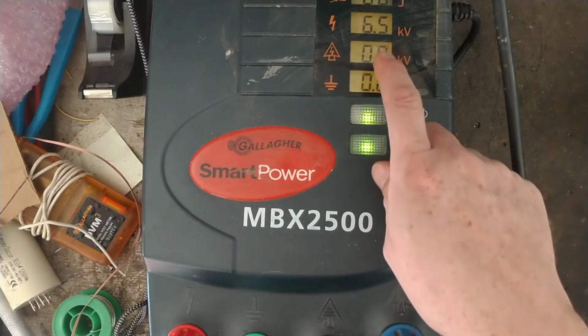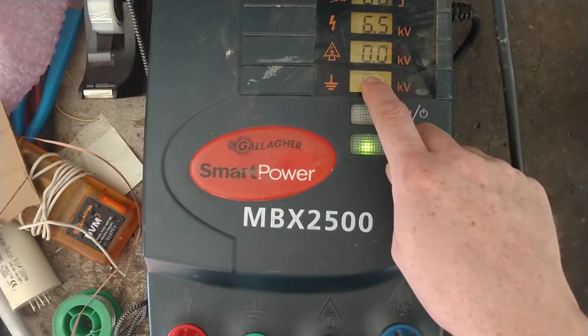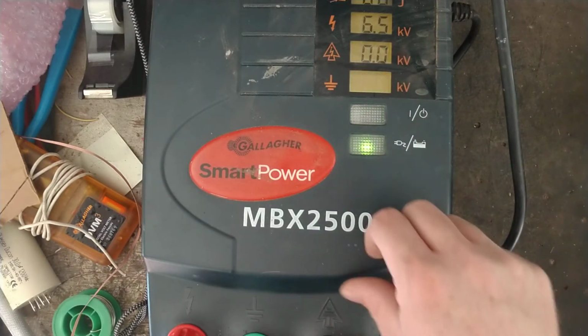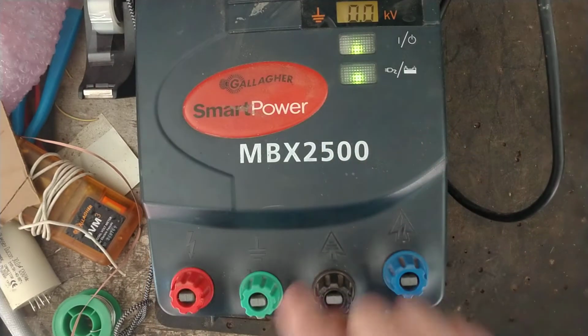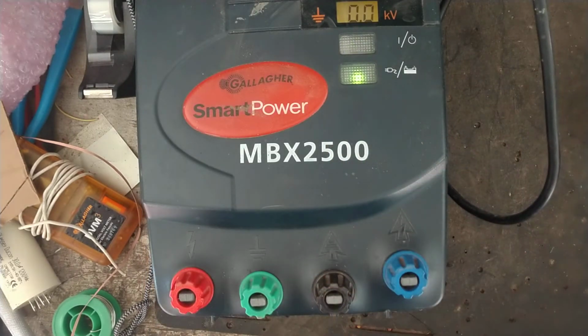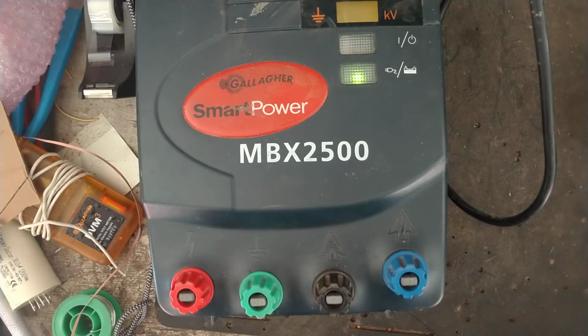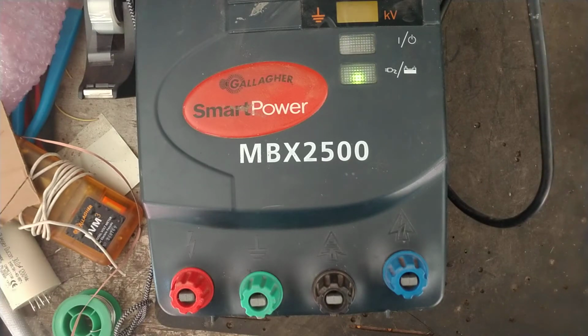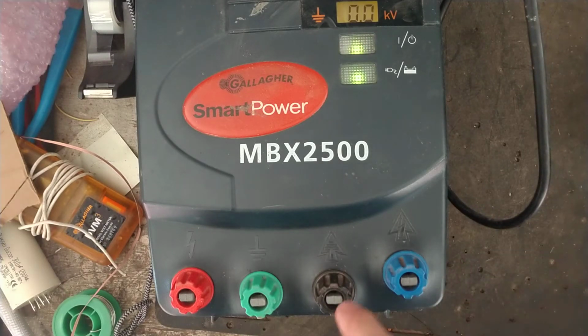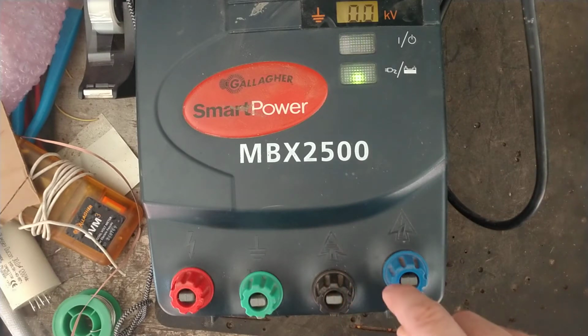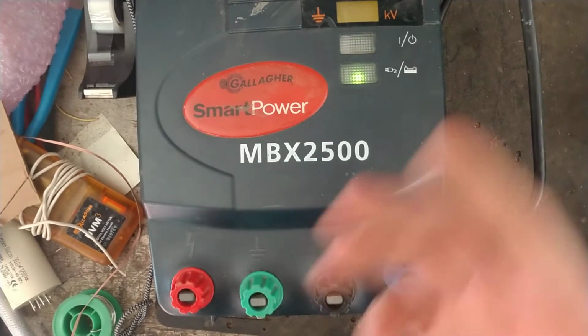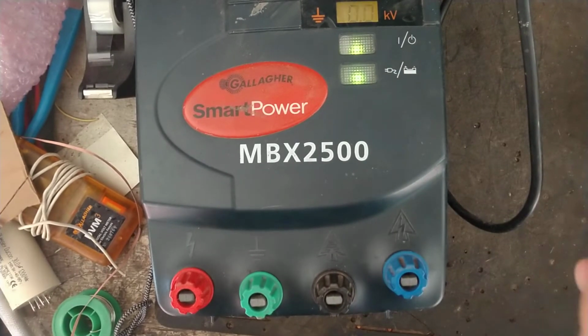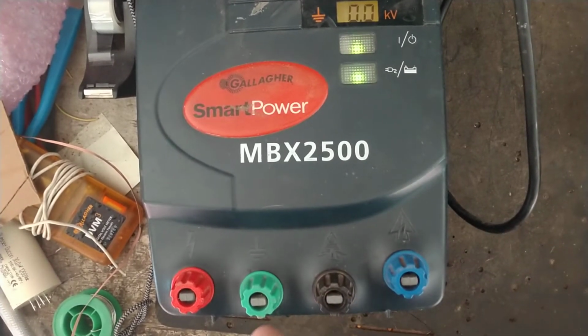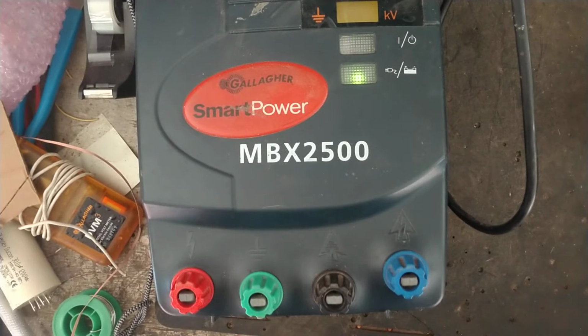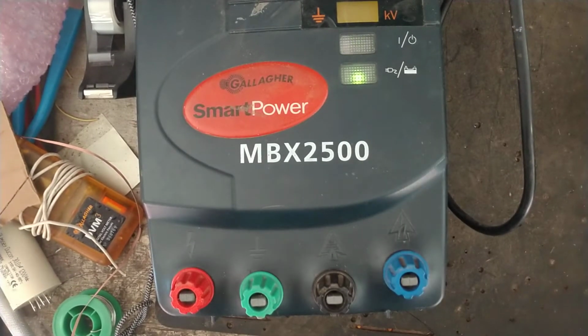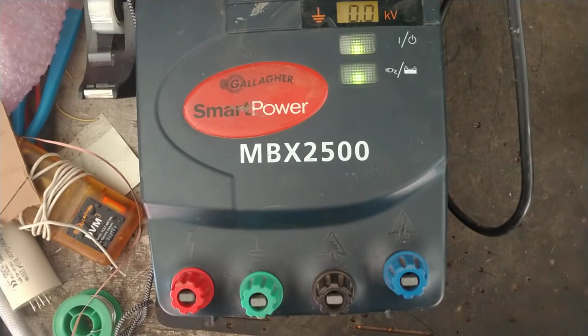So it needs a pretty good ground system. If for some reason you had this black wire hooked up, you don't hook it up to the ground system itself. You knock a separate ground rod in, maybe 5 to 15 feet away, tie it onto that, and electronically, through magnetic fields, it will monitor the ground side of your ground system, but you don't want to physically tie into the ground system itself. I believe that's what the book says.